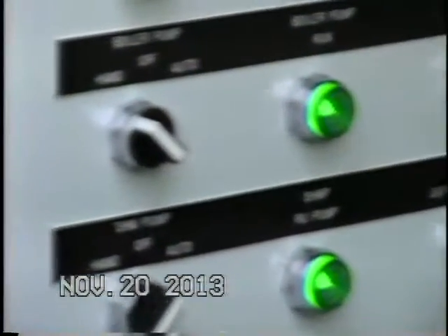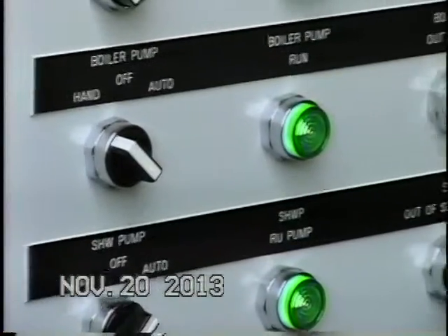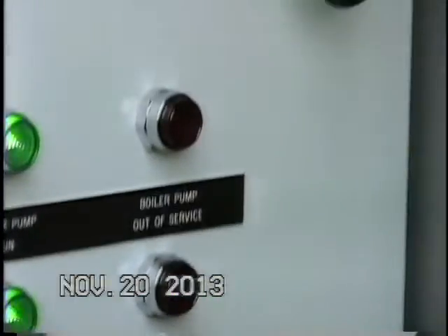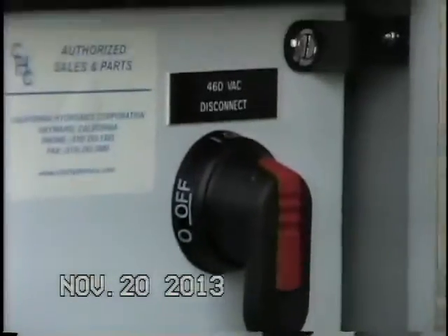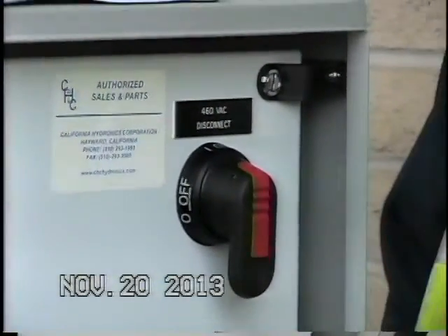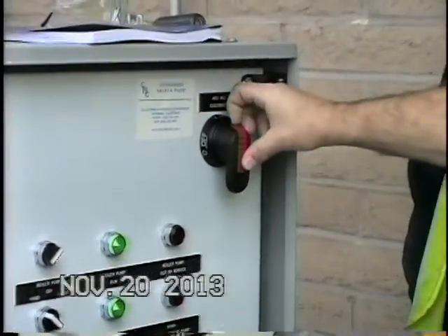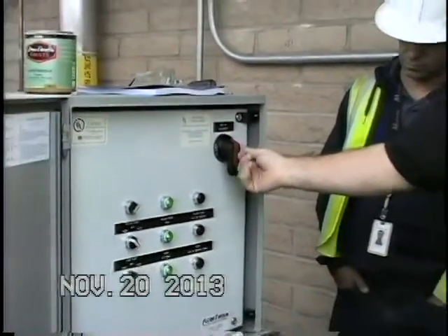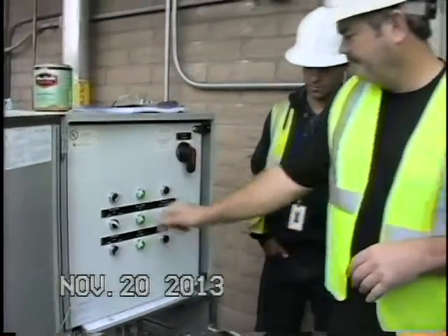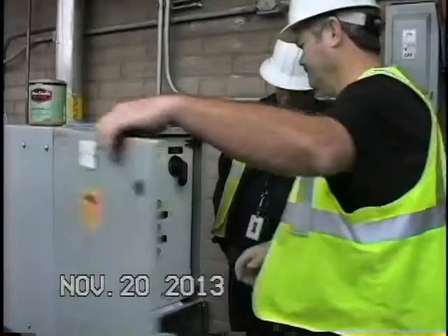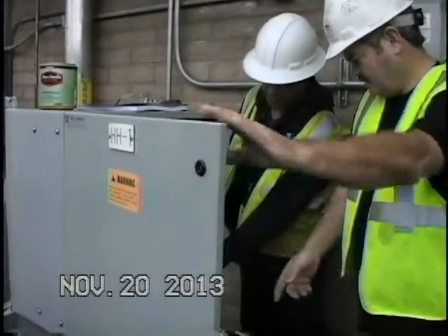And then that way it bypasses anything that's out in the system and it'll run in hand. And also this is where you tag it out. If you shut this off, I don't want to shut it off because we might overtemp the boiler or something like that. So you shut it off and then this handle pulls out and then you just put a lock on this handle right here. Okay. There are complete wiring diagrams inside of it, laminated.